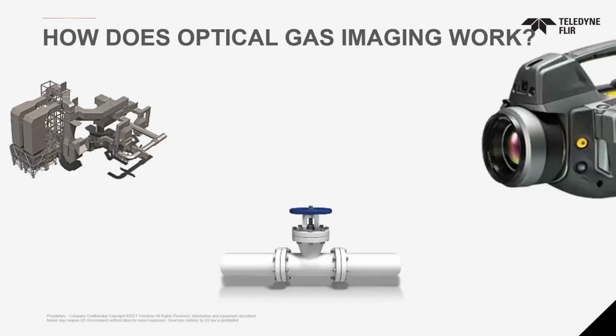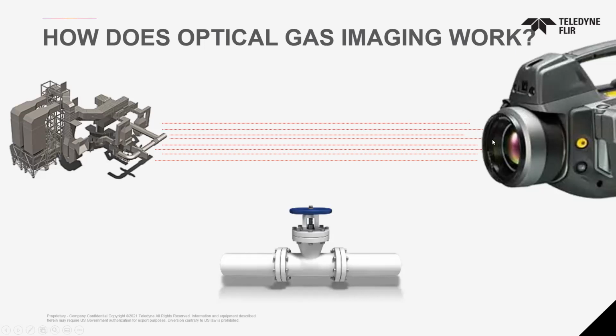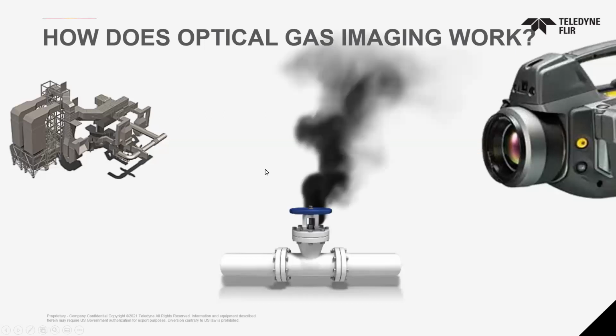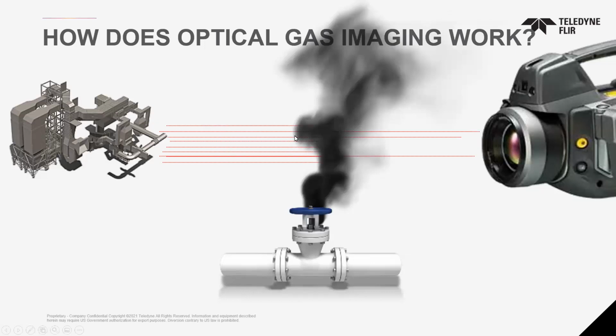But for the gas leaks we can't see with our human eye, how does that work? Every object emits energy in different wavelengths. So when we have an object—a valve, a skid, whatever—it's emitting energy, and if it has a leak, it sends that energy toward the camera. You point the camera at it, and the camera detects that. If there's a leak in front of the object, when it sends those wavelengths back to the camera, some of them get blocked, and in our camera, it looks like smoke.